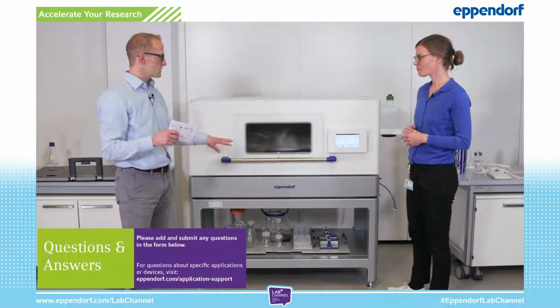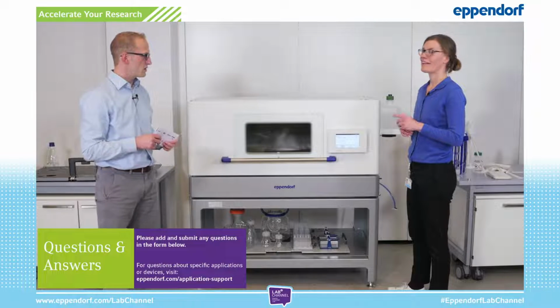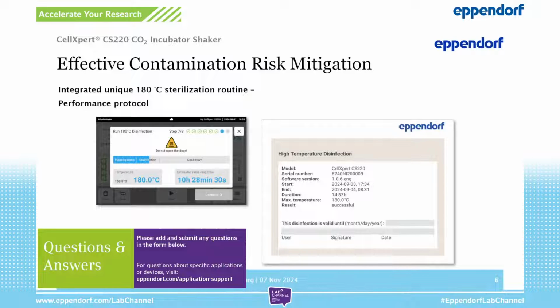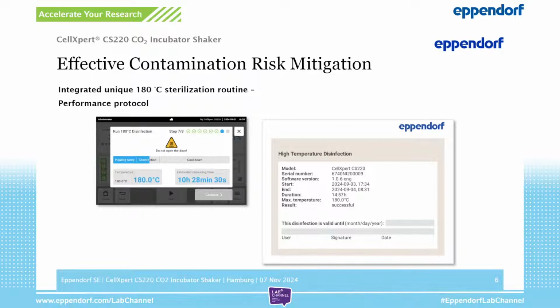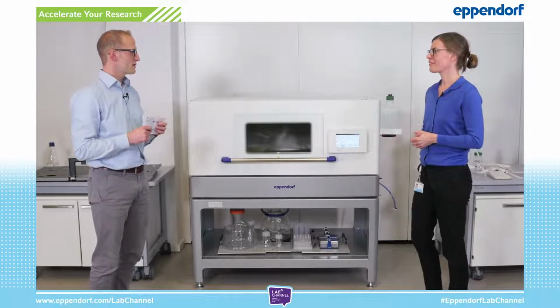And after the sterilization, once everything is done, do you get any kind of documentation in there? Exactly. So when you look at the screen now, the display says it ran successfully, and then you also have the chance to extract a performance protocol, indicating the model number, serial number, plus also start and end time, the duration and the maximum temperature, and the most important, that it was successful, and you can sign it and put it into your documentation. And I also see there's a field for a signature, right? Exactly. Somebody has to take the responsibility for signing that. Okay, now it complains it's not properly closed. Yeah, the door is hooked up here, long door opening.